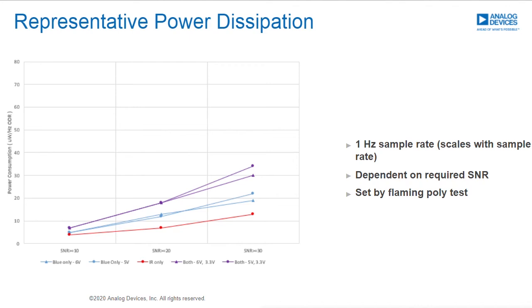So 20x the signal versus the noise is a typical level that any algorithm will be able to deal with. And what you can see here is that, basically, if you're just trying to detect smoke with infrared, which would be a way to just detect that there's something there without even flashing the blue LED until you've actually detected something with IR, you can operate at less than 10 microamps, or less than 10 microwatts of average power. And then once the infrared signal actually detects something present, some type of smoke present, you can start to flash the blue as well, at which point you're going to go up to maybe about 15 microwatts. Okay, so it's a very low power solution.